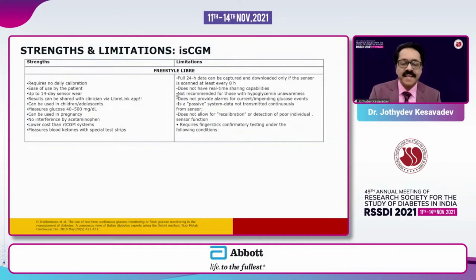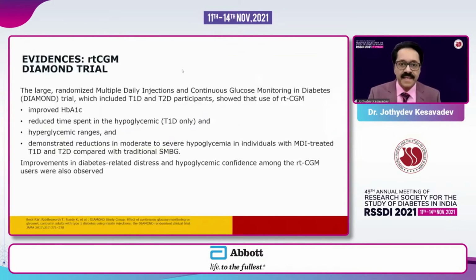And what about the strengths and limitations with an intermittently scanned CGM? The strength, I would say, is that no calibration is required. And the biggest drawback, I would say, is that you have to scan the sensor every 8 hours, at least 3 times in 24 hours. Otherwise, the data will be lost. If I forget to scan my sensor, which happens very often because I don't have diabetes, I will lose the data. So that is the biggest drawback. And it does not allow for calibration or recalibration. And you need to retest when you are making dosing recommendations.